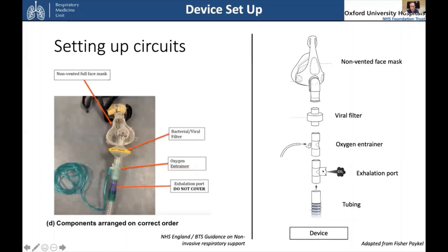This is a really important bit that's worth making sure is present - you've got your exhalation port here, which allows the CO2 to come out. If this wasn't here, the patient would just be breathing in pressure from the device and breathing in and out the same air, and the CO2 will increase. I remember Chris in the first wave came across a patient who didn't have this, and they became CO2 narcosed on the ward. Luckily he picked it up and sorted the patient out. But it's an important thing to check for.